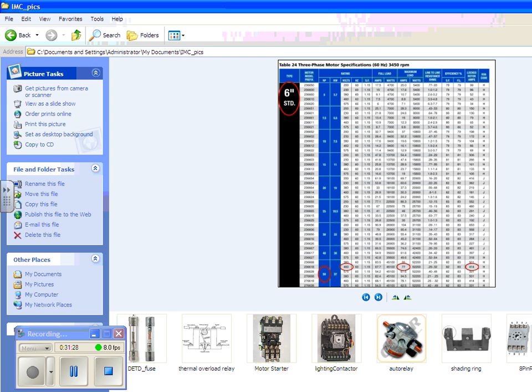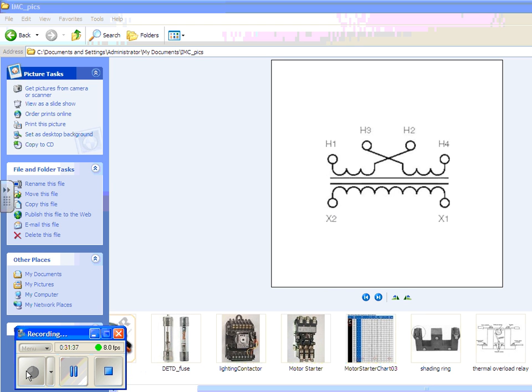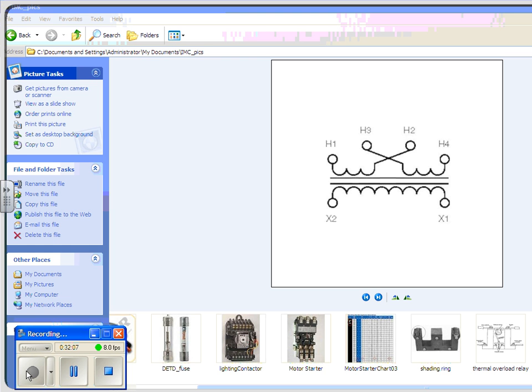All right, one last thing I want to talk about today is the control transformer. Okay, the main thing you need to know about a control transformer is that they're all dual voltage transformers. But they only operate on 2 voltages, 240 and 480. That's the supply voltage. What comes out the bottom end is 120 volts every single time because you're putting in the 240 or the 480 in the proper way. In the top, we can do this because we have 2 sets of windings in the top of the transformer.